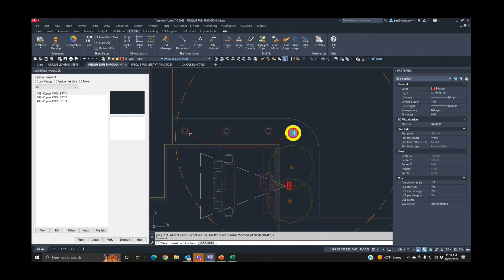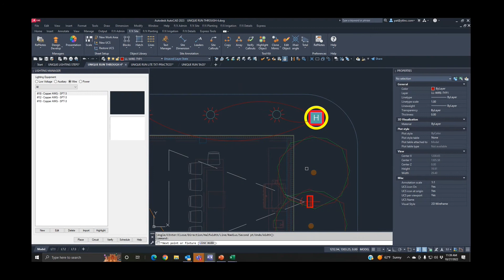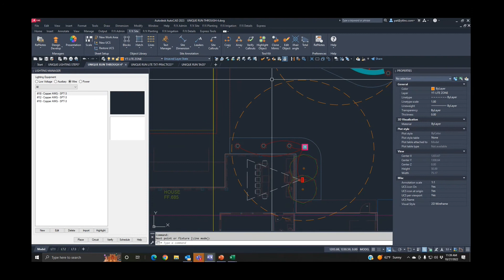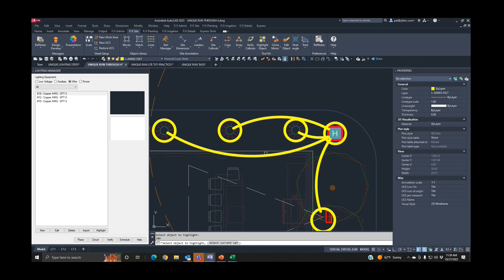We can go back out, hit our fixture, it turned yellow, we're good. We can hit our enter key a couple of times to repeat the command - we'll go fixture, IntelliHub, fixture. So we should have wired all 4 of our lamps. We use our highlight object tool, we can hit our IntelliHub, and everything turns yellow. Everything has a yellow circle on there, which means we've got good connections in that zone.